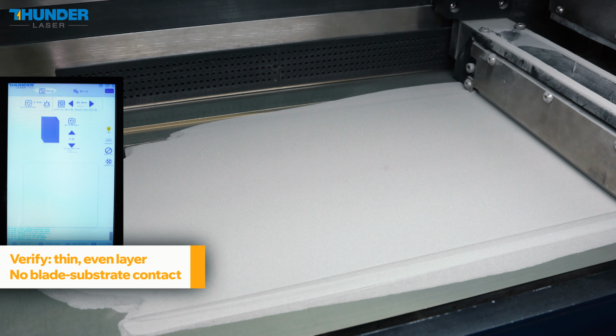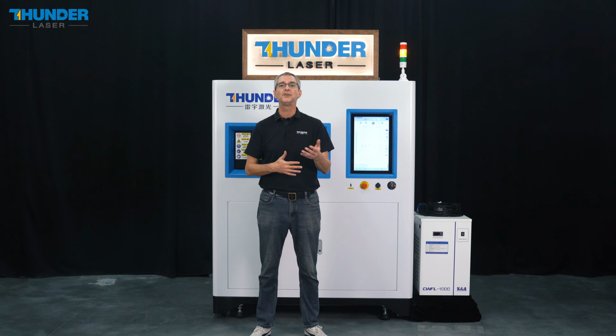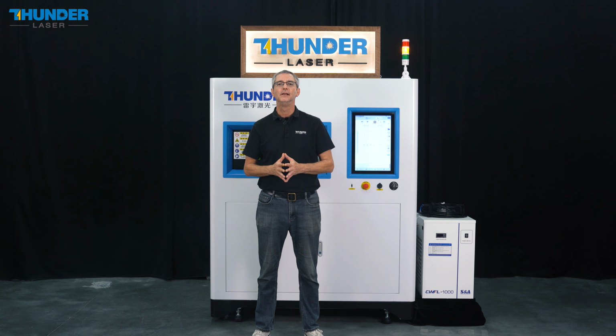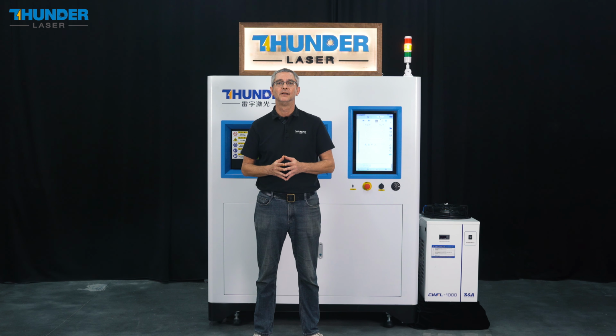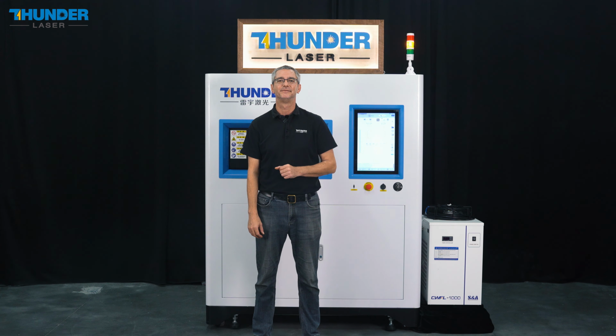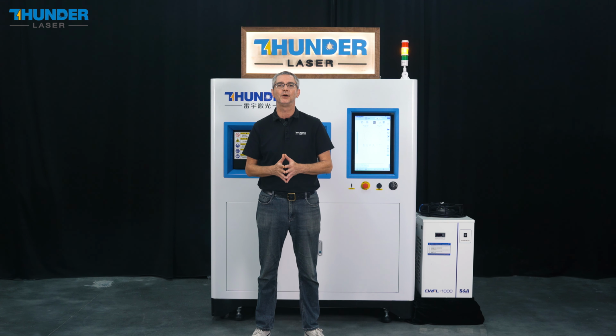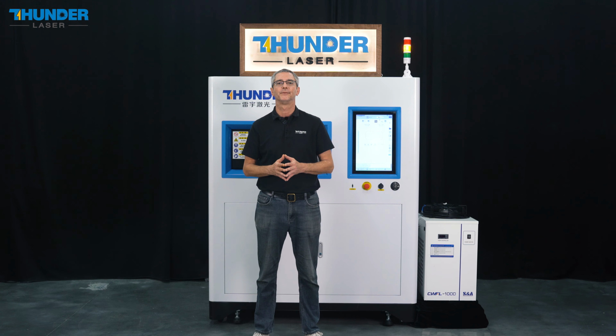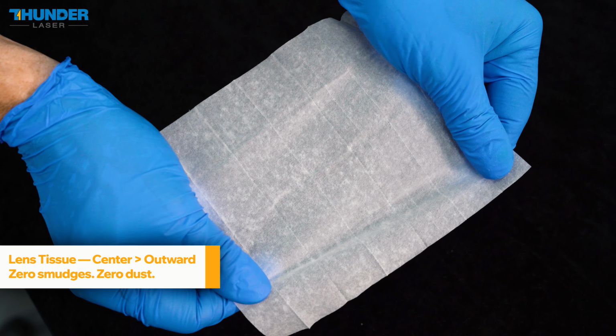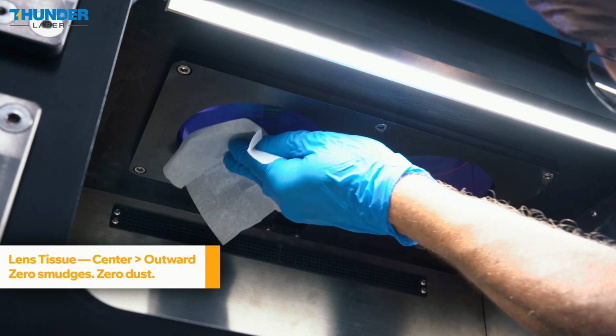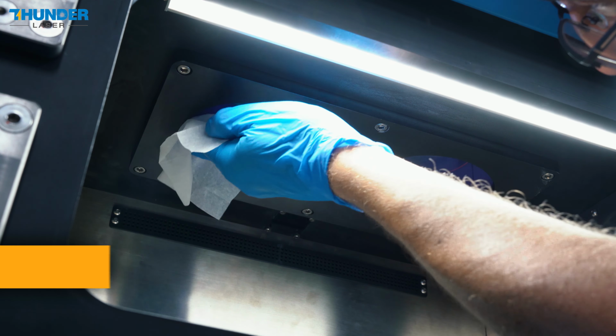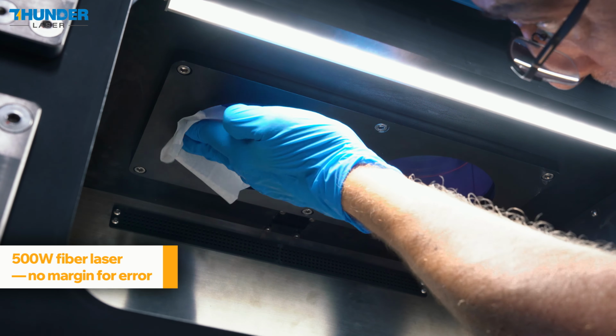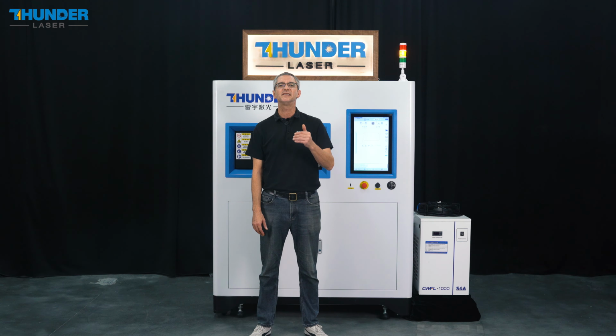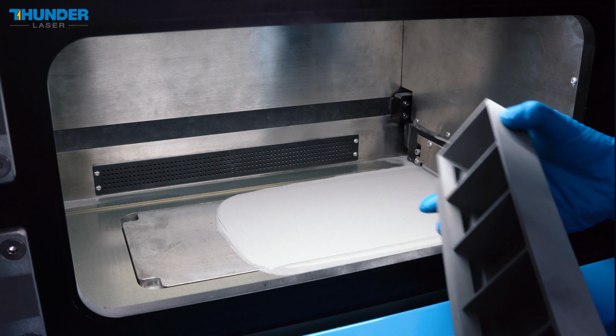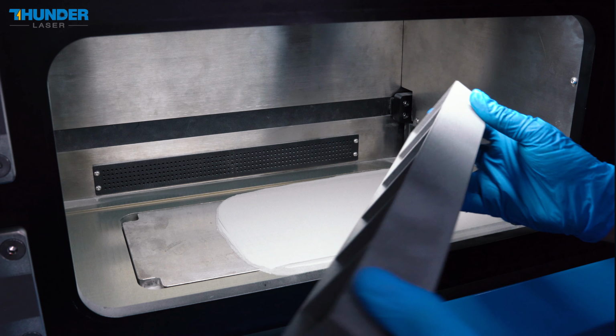You need to see a thin, even powder layer. What you are about to see is the last precision step before this machine is clear to print. And it takes just 30 seconds. The protective glass cover at the top of the chamber sits directly in the laser beam path. Use lens cleaning tissue only. Wipe from the center outward in smooth radial strokes. A single smudge here will defocus the 500-watt fiber laser from layer 1. This step takes 30 seconds. Do not skip it. Install the suction box with its air outlet facing inward.